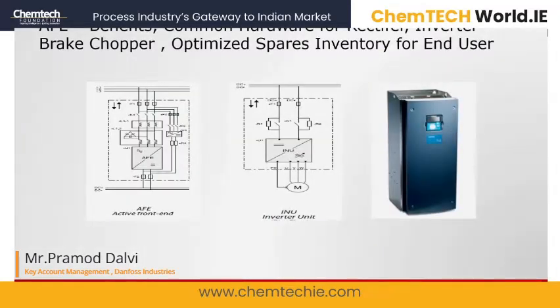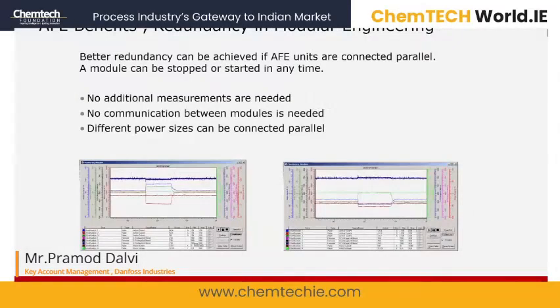In Danfoss drives, we have a modular construction where the active front end and the inverter are the same unit. So a user has the advantage that you can keep only one unit as a spare. Otherwise, the spare cost will also go up. It is programmable: that same unit can be programmed as an inverter, or it can be programmed as a converter. And it's free software. Danfoss has no charge to do this. It's not licensed software to convert an inverter into a converter. The same active front end can also be put in a modular construction where it can be programmed for redundancy. So in case of failure of one unit, the other unit can work without any stoppages.